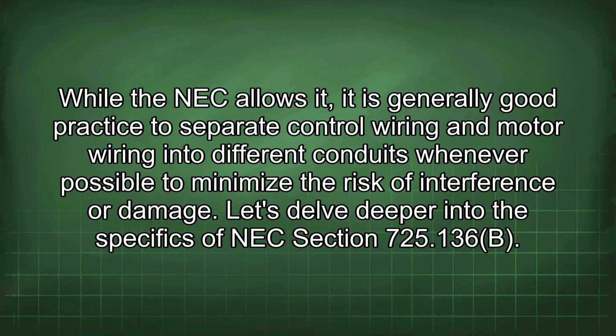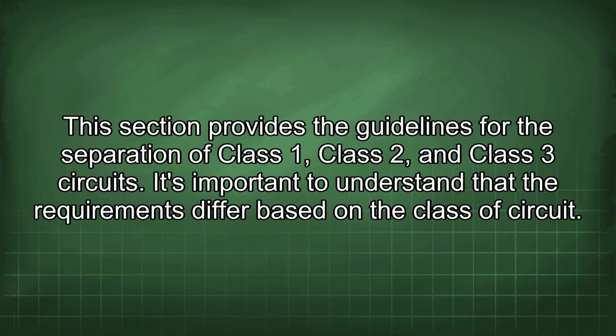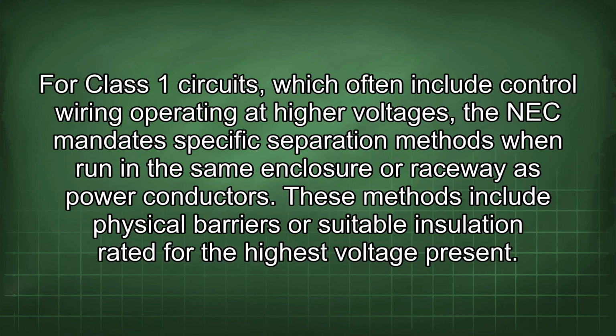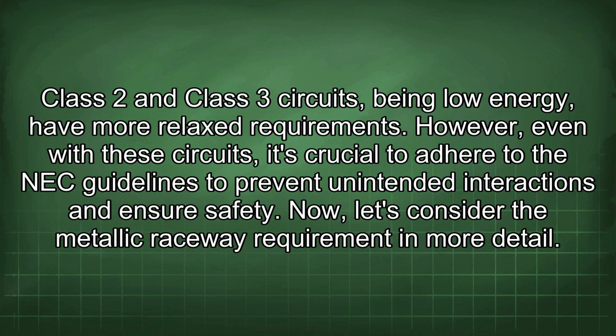Let's delve deeper into the specifics of NEC section 725.136(B). This section provides the guidelines for the separation of Class 1, Class 2, and Class 3 circuits. It's important to understand that the requirements differ based on the class of circuit. For Class 1 circuits, which often include control wiring operating at higher voltages, the NEC mandates specific separation methods when run in the same enclosure or raceway as power conductors. These methods include physical barriers or suitable insulation rated for the highest voltage present. Class 2 and Class 3 circuits, being low energy, have more relaxed requirements. However, even with these circuits, it's crucial to adhere to the NEC guidelines to prevent unintended interactions and ensure safety.